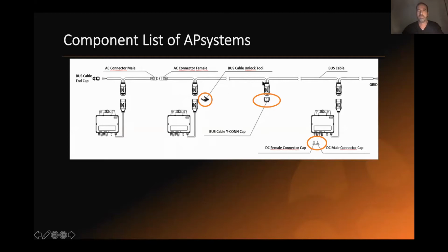And if you don't use one drop, we have a cover too, and then you plug and play the bus cable into the AC connector. So if you have an installation with 5 micros, you will order an AC cable with 5 drops, or AC connectors, with 2 meter spacing or 4 meter spacing, whether you are in portrait or landscape. And you also have all kinds of accessories, AC connectors, male, female.